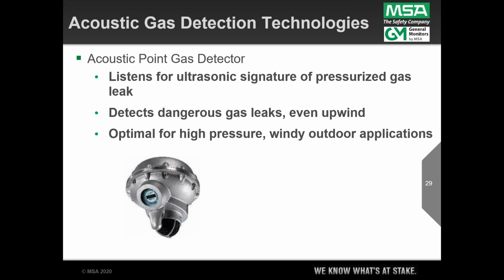Where is it really optimal? It's really optimal for high pressure, windy outdoor settings where the wind is always blowing, and you could put a line of sight, you could put a point detector, but we're just not 100% sure that because of the windy situation we're going to sense that gas. So a prerequisite to using this is that your hazard is pressurized. It's a pressurized gas leak. It is not capable on liquid spills where you just have a pool of flammable. It's not going to sense those.